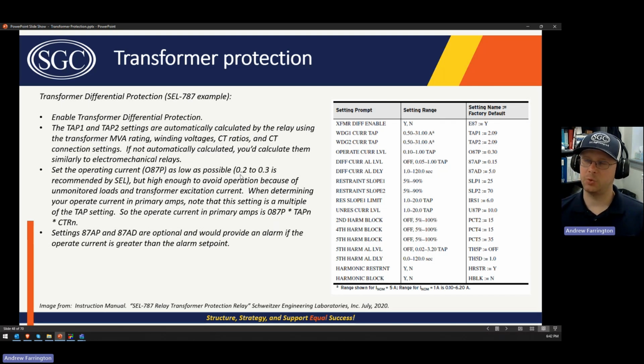Okay, so what's the actual current seen by the CT that causes it to operate? You take that per unit setting and then you multiply it by the tap for that particular CT. So if you wanted to know what the high side current needed to be in order for the relay to operate, you'd take say the setting was 0.2, you multiply it by tap 1, and then you multiply that by CT ratio 1, and you can calculate the primary amount of fault current that would be required for the relay to operate. All right, when determining your operate current in primary amps, note that the setting is a multiple of the tap setting. Yeah, exactly. So the operate current in primary amps is the setting times the tap times the CT ratio. Yeah, just like I said.